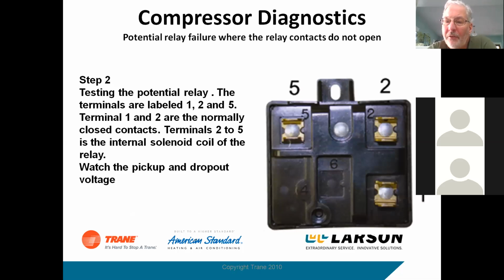Potential relays, and you see these on our hard start kits. If you buy a Trane or American Standard hard start kit, it's got a potential relay and a capacitor in it. Copeland uses these. They're pretty universal. There's different pickup and dropout voltages, so you can't just throw a generic on there and expect it to work. It could be that it's a higher voltage, lower voltage, and if the voltage doesn't come up to speed, like if you're running low voltage, these things will stay in the circuit and then eventually burn themselves out. So pickup and dropout voltage is important. Make sure you match that when you're replacing a start relay.